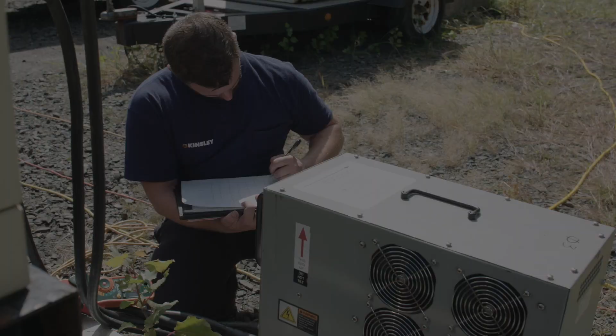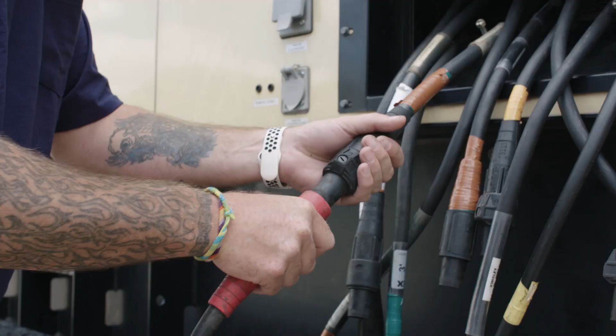The second reason why we would perform a load bank is it's real common on a diesel generator. We have what they call wet stacking. Wet stacking is where raw fuel that doesn't get burned in the cylinders makes its way into the exhaust and sticks to the inside of the exhaust. This happens for a few different reasons.